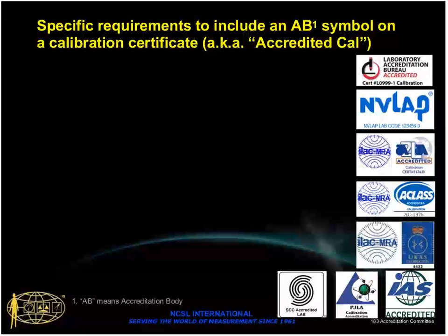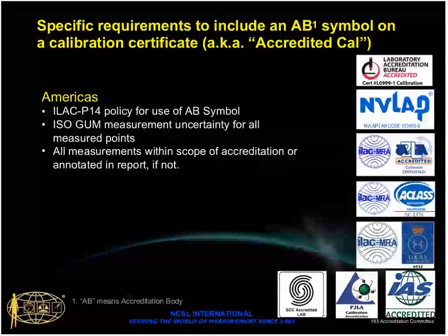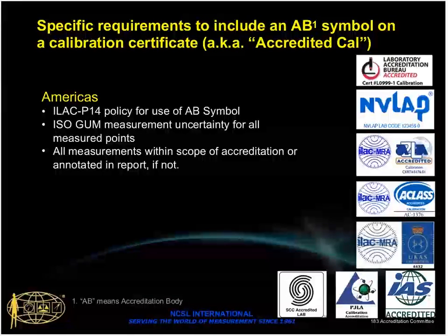Okay, thank you, Bob. The first point to make about putting the accreditation body's mark on a calibration certificate is that the work must comply with 17025. This slide doesn't make that clear, but the point here is that throughout the world, laboratories that use the accreditation mark on the certificates shall comply with the standard ISO 17025. The other documents that are mentioned are, I would say, interpretations of it. From a manufacturer or a laboratory's point of view, they might see it as additional requirements. We could argue about that.